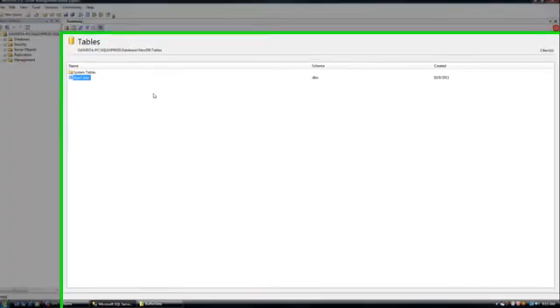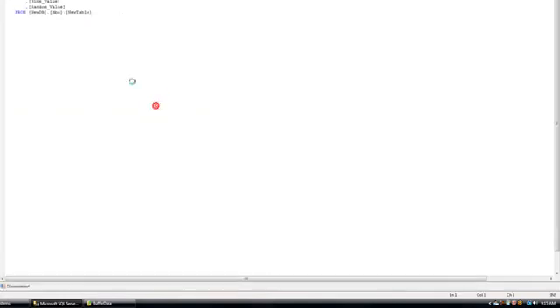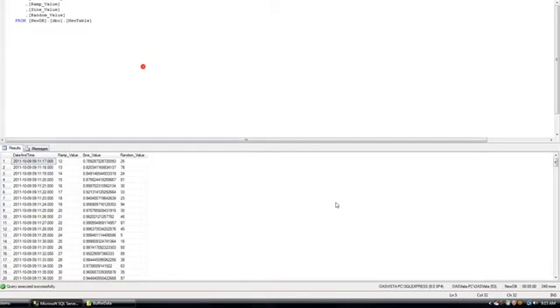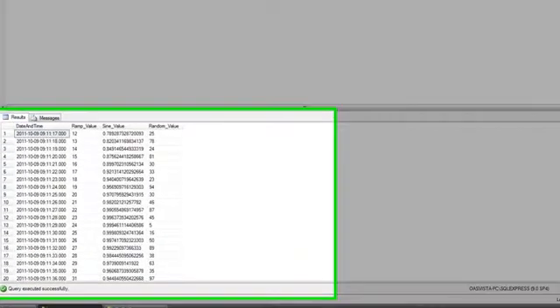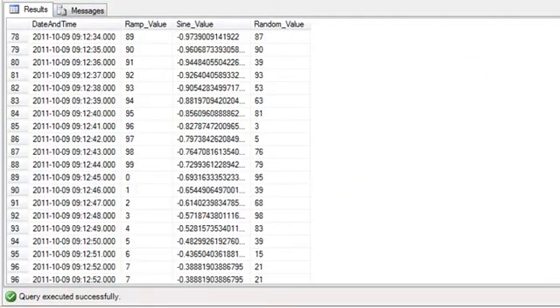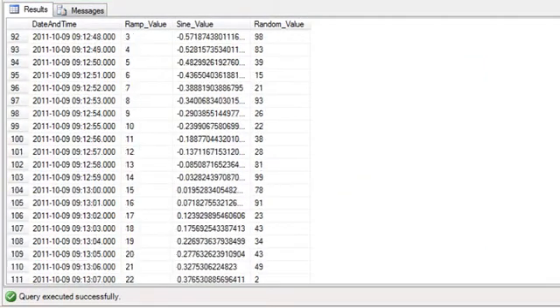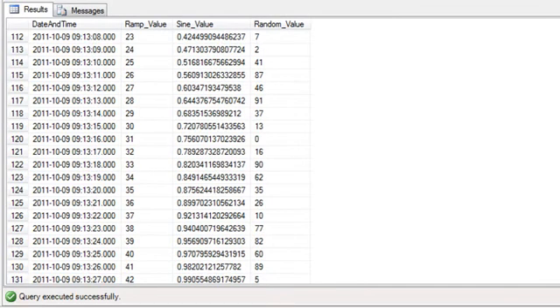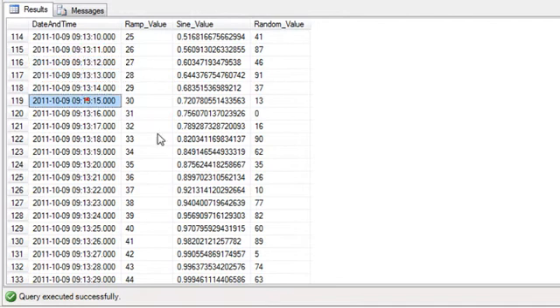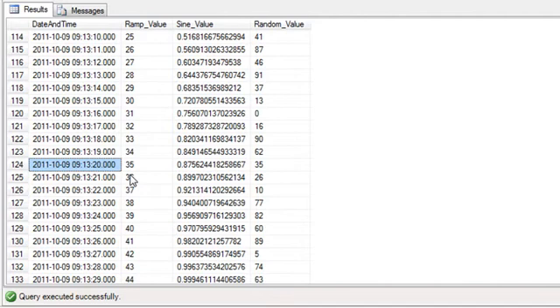So let's go back to the database engine and let's re-query that same table. If we execute that, we can now go down to the time that we set at 9.13 and 12 seconds is when we shut it down. And we see that we have the values being logged for the time that the database engine was down. That's demonstrating when we have a database engine failure.